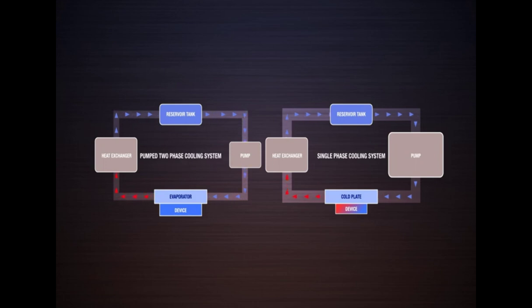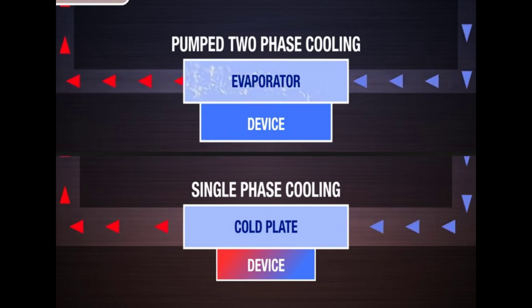Pumped two-phase, or evaporative cooling systems, use the same basic system-level components as the pumped single-phase system. However, pumped two-phase systems typically use refrigerants as the working fluid. Through refrigerant selection and appropriate controls, the refrigerant is designed to boil as it acquires heat from the hot surface of the device. More heat can be removed through the boiling process, otherwise known as latent heat, than through sensible heat with single-phase cooling. Boiling across the entire evaporator surface offers a further advantage in that the evaporator will have a very uniform surface temperature, typically within a few degrees.